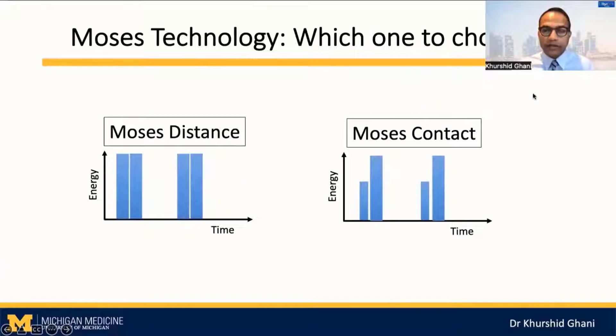And so what are the advantages of using Moses technology? We studied this in the laboratory and published this in 2019, where we compared short pulse, long pulse, Moses contact pulse, and the Moses distance pulse on BegoStones with the laser fiber touching the stone on contact, fired for 200 seconds using a pulse energy of 1 joule and 10 hertz. And you can see at the end of all these experiments, we found that there was one pulse mode which led to more fragmentation. And that pulse mode was the Moses distance pulse. And so we found that this particular pulse was pretty unique, and it led to around 30% more fragmentation.